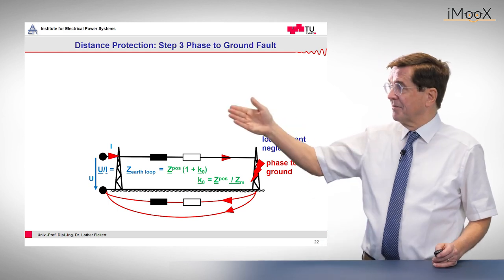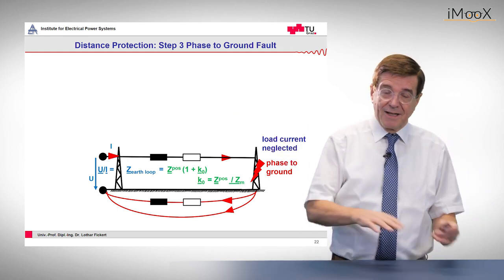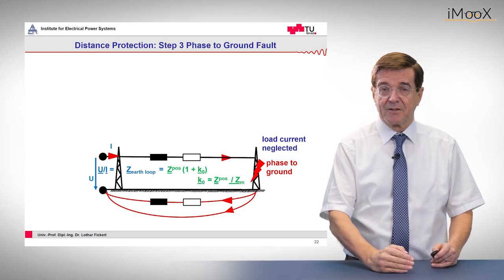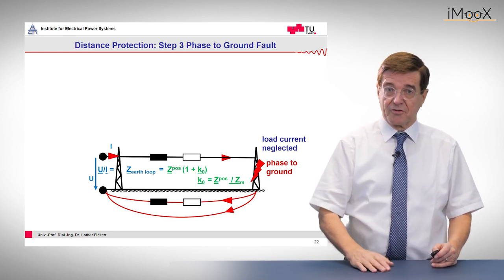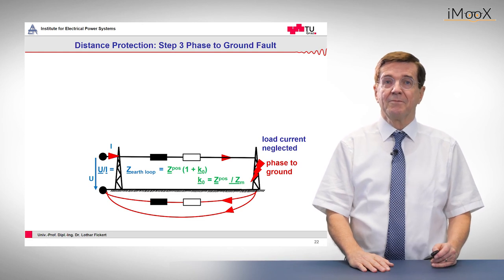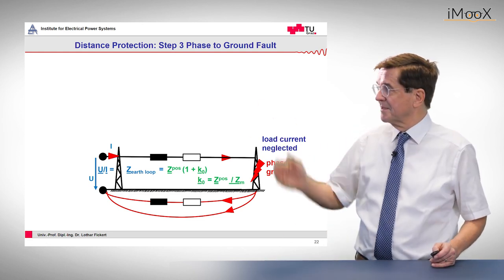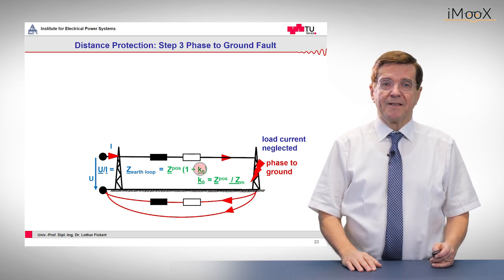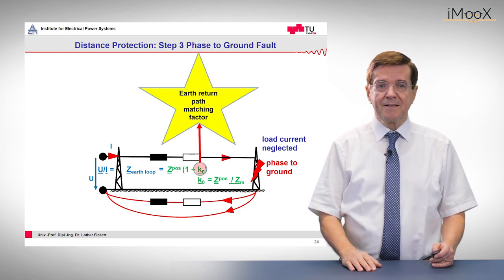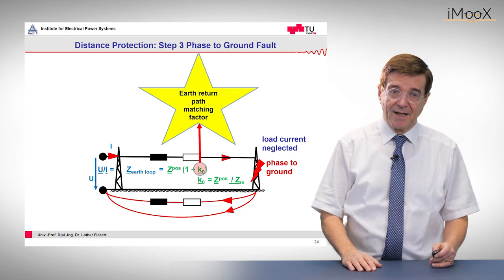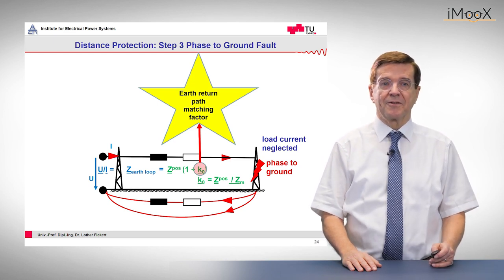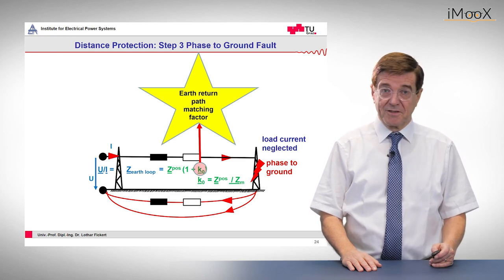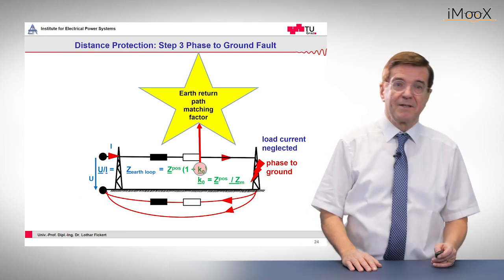We have this together, and the relation between the earth impedance and the positive sequence line impedance is constant. So we can express the whole loop impedance in these parts. To find out the positive sequence impedance, which we would like to have, we must know the earth return path matching factor by measuring the positive sequence and the zero sequence impedance.